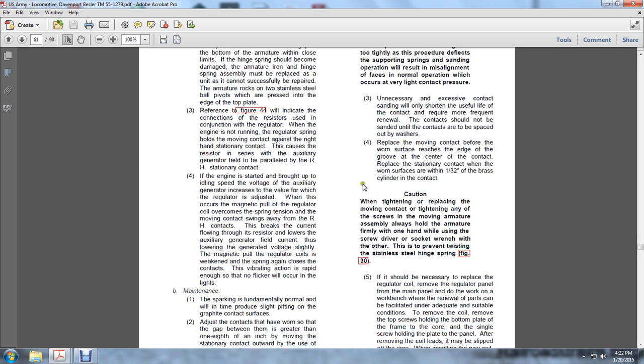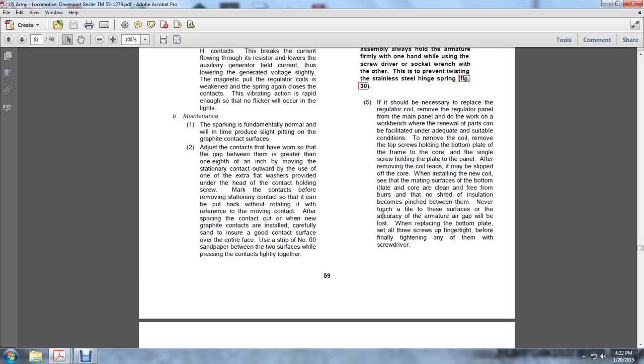When tightening or replacing the moving contact, or tightening any of the screws of the moving armature assembly, hold the armature firmly with one hand while using the screwdriver or the socket end of the wrench with the other. This prevents twisting of the stainless steel hinge springs, as in Figure 30.